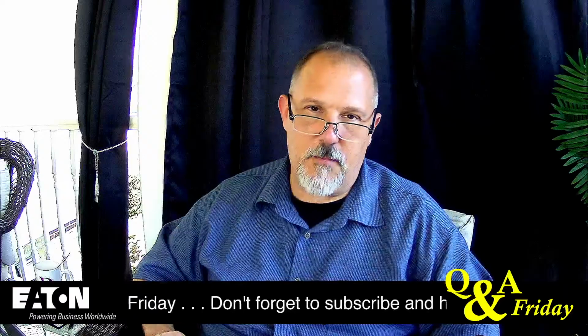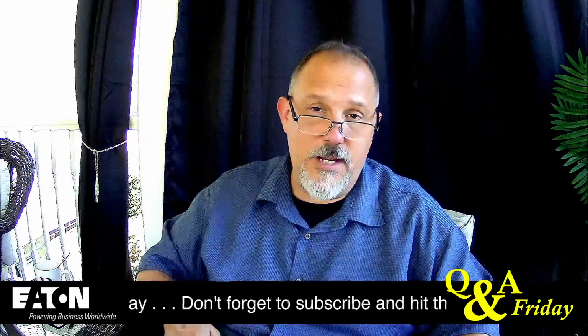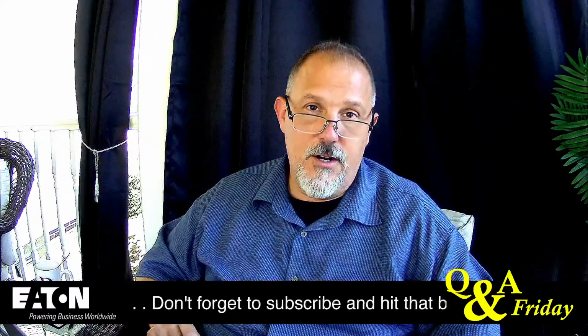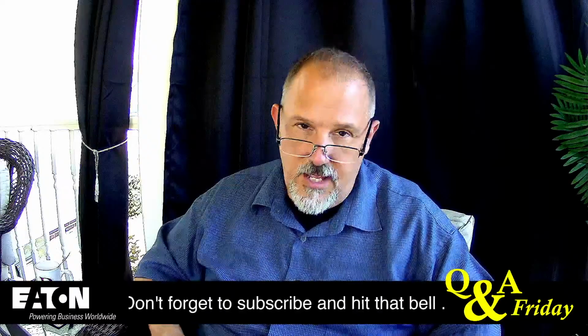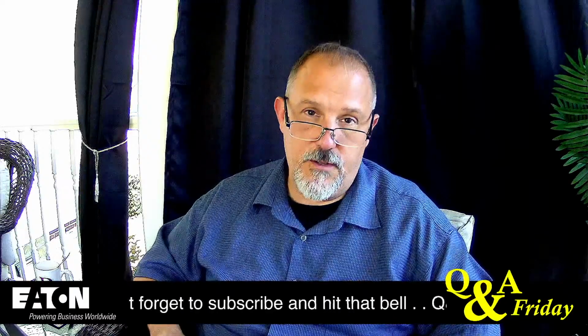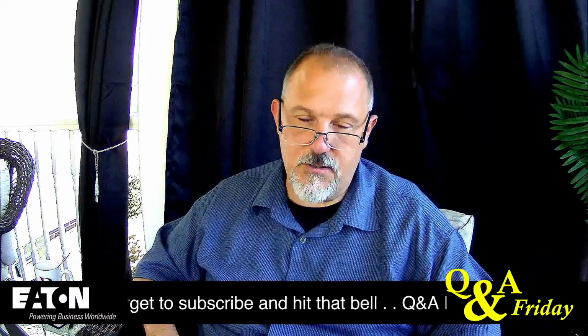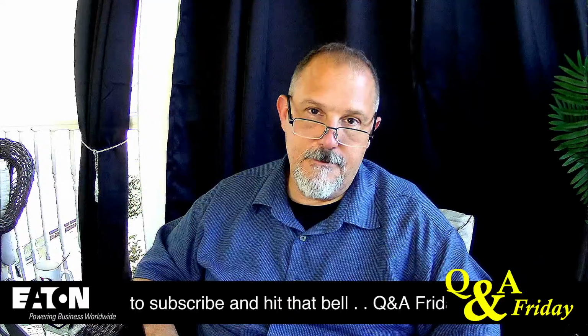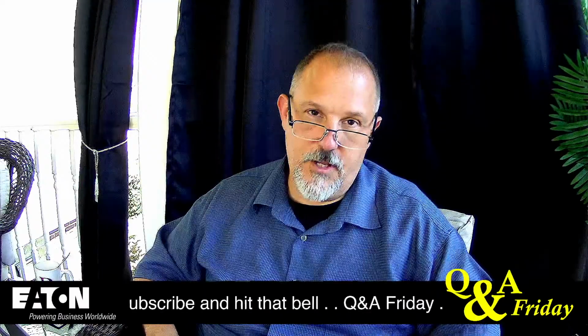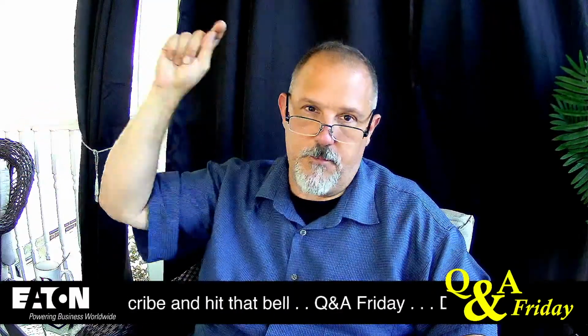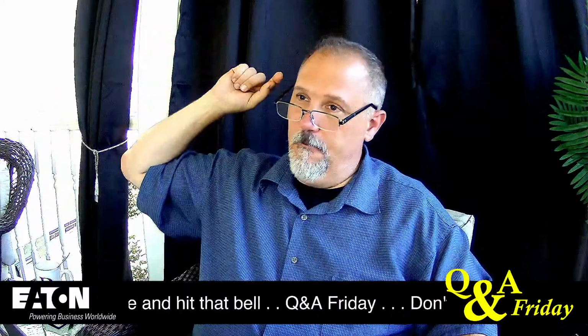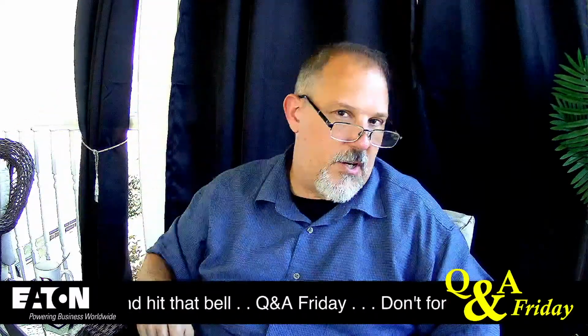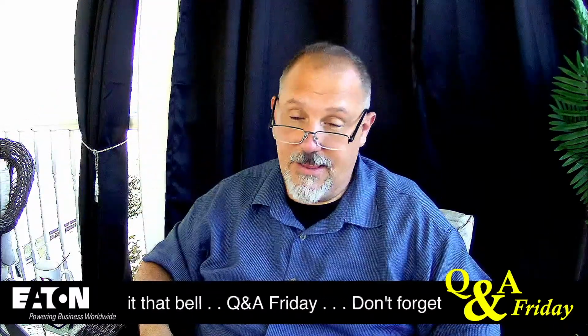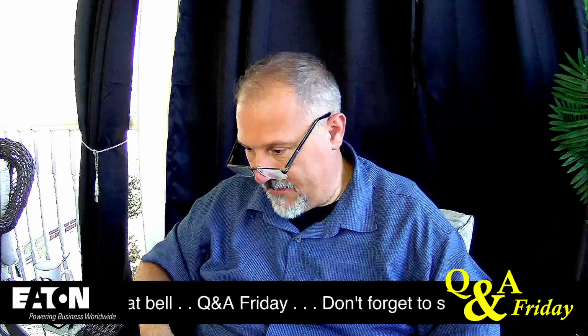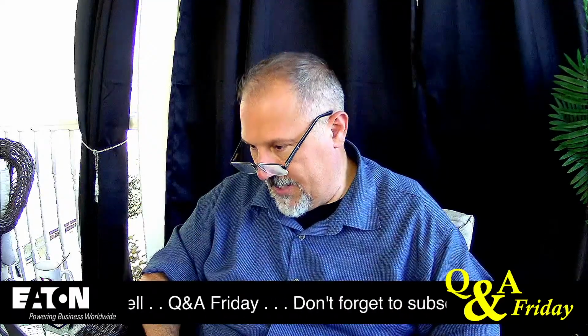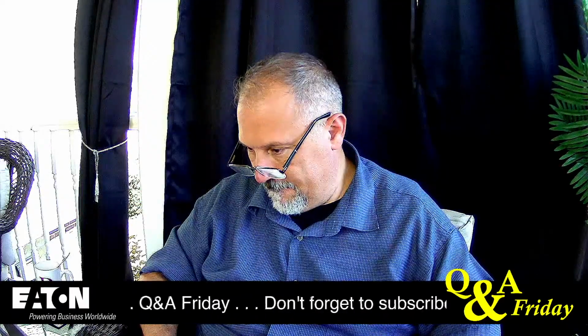All right, so that was my journey on the fire pump question. It was, do I need that neutral, even if I'm not going to use it from the utility? And the answer to that is yes. Yes, you do. You've got to land it in that equipment. You have to bond it in that equipment because that is your fault return path. And that's all I've got to say about that. Thank you, Phil, for reminding me to talk about that.